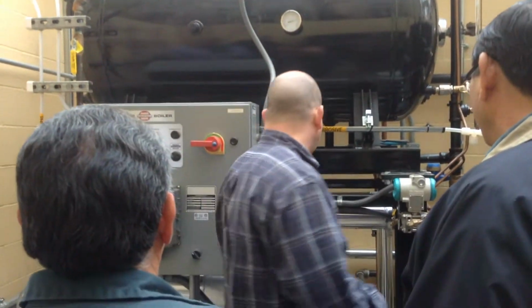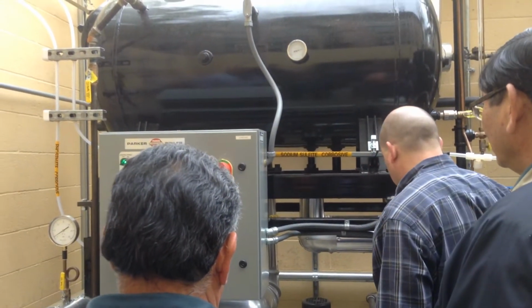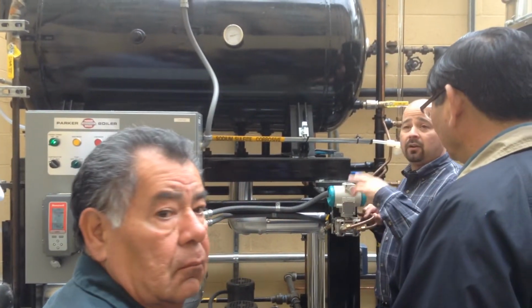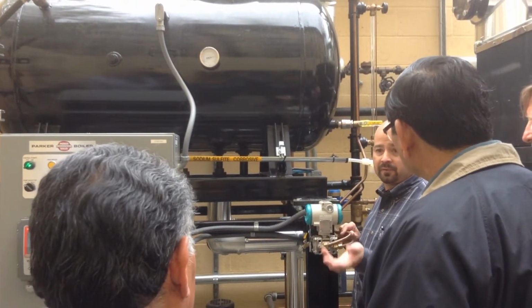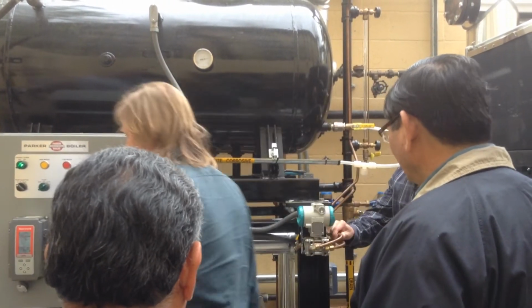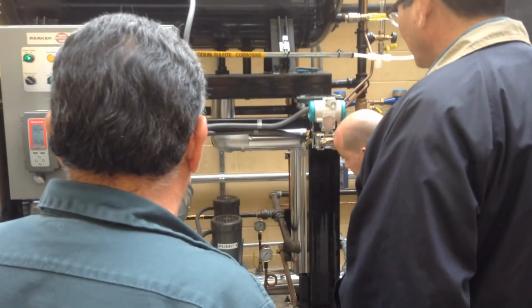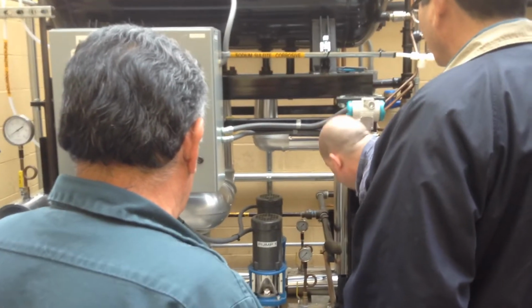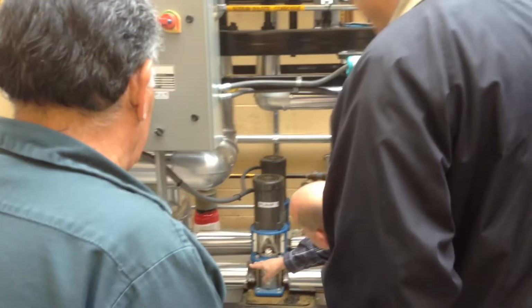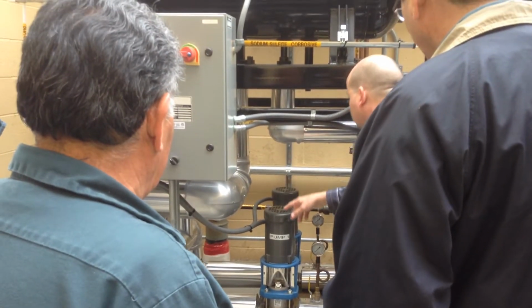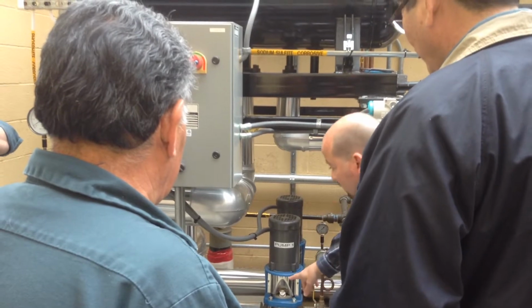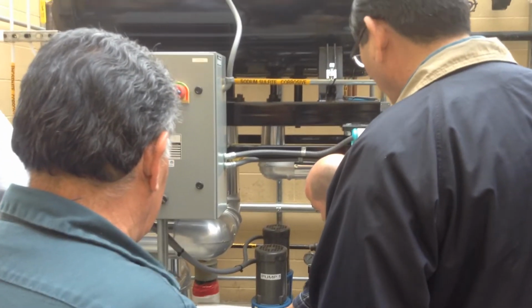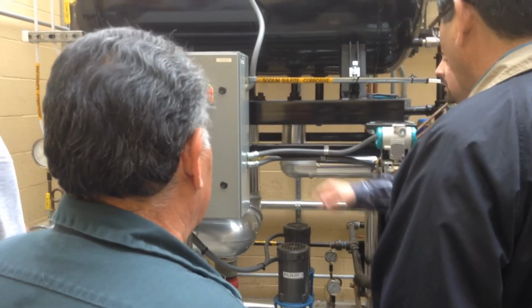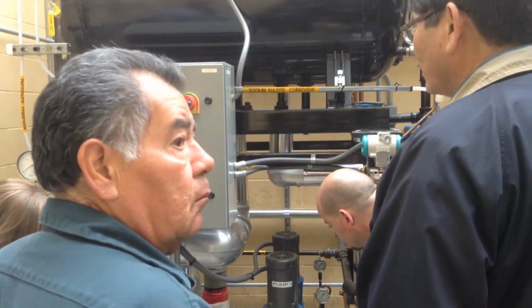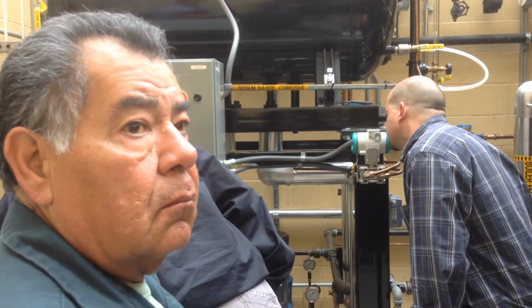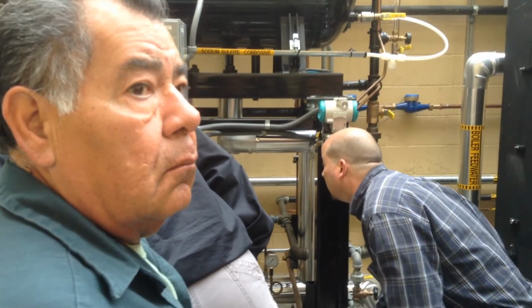Okay. So the pumps are centrifugal multi-stage pumps. Again, you have complete redundancy, and it also alternates every time it flips between pumps to divide the wear and tear. You should have pump strainers. We're going that way. There's one main strainer, or they're insulated over, I'm not sure, but there should typically be a pump strainer on the inlet of the pump. Hey, Mark? I have to look at the drawing on that. Do you have a strainer on the inlet of the pump here? Is there a strainer hidden underneath insulation or something? I'd have to go look at the drawings.